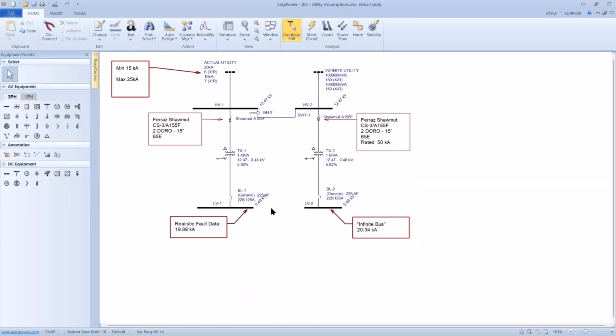And what I want to show is the impact on doing the calculations based upon all these choices. So first of all, I'm starting off comparing the actual data versus an infinite source data. And just for grins, I've made the subsequent circuit identical on both sides. And I've connected the two, which is the way EasyPower won't accept a one-line diagram where there's isolated sources. So rather than have two feeders or two drawings here, I connect them with this virtual cable and leave the switch open.